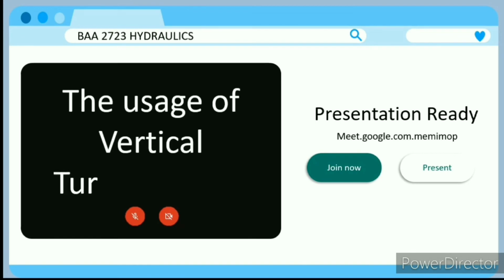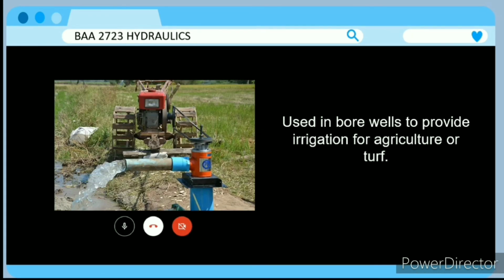Now, I'm going to tell you the usage of the vertical turbine pump. Vertical turbine pumps are typically employed in locations where submersible pumps are not feasible. This is frequently because the flow is too high for submersibles or the owner prefers a traditional top-mounted motor. Vertical turbine pumps are used in bore wells to provide irrigation for agriculture or turf. They are also utilized to provide groundwater for communities that don't have access to surface water, as well as plant makeup water and fire water for industrial operations.